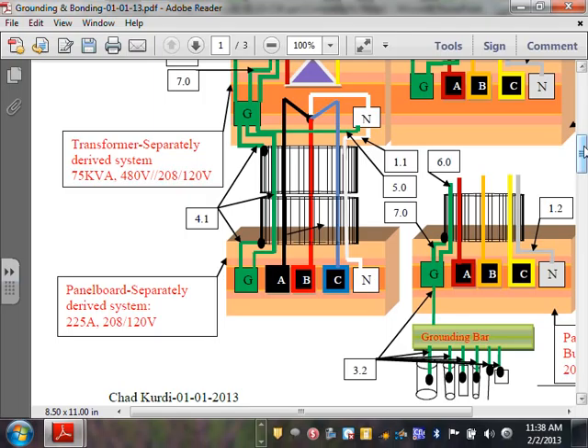Why supply side? Now, confusing me, Chad. Why is it supply side? Because if you have a separate derived system, anything on the line side of the circuit breaker, which is mostly in the panel, is called supply side. It's like the service. Imagine as if you have created a new service. If you have a separate derived system, you create a new service, right? You bonded, you went to the ground, and also the panel, when you bond the panel into the transformer enclosure, the two enclosures together, you have to pull a wire between them because you're using flex. That wire is not called equipment grounding conductor. It's called supply side bonding jumper. Who cares? The question is, who cares, Chad?